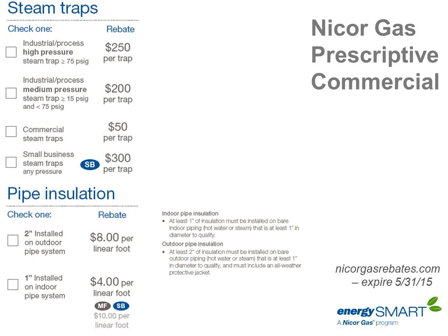And then there is a small business steam trap incentive. So instead of $50, it's $300. So that's a good target as well if you got a small business on steam. As you know, if the steam trap fails open, nobody ever notices. It still heats the space, and the way they control capacity is by opening the window. So fixing these steam traps can save a lot of energy. Rebates for pipe insulation, depending on whether it's indoor or outdoor, regular commercial, multifamily, or small business.